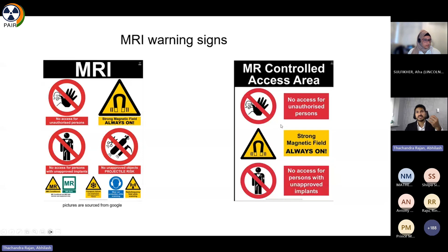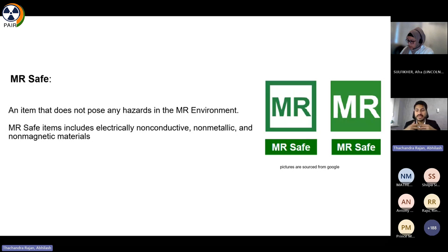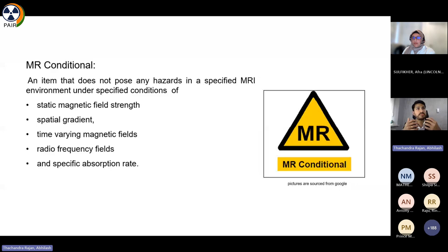What is MR safe? Any item that does not pose any hazards in the MR environment, which includes non-magnetic, non-metallic, or non-conductive materials. MR conditional items are similar to MR safe items, but there are conditions for them. Those conditions relate to field strength, spatial gradient, time varying magnetic field or the gradient field, radio frequency fields or the RF fields, and specific absorption rate. MR unsafe items are not allowed inside the MR environment. Mostly they will be ferromagnetic materials, and they will be denoted by this symbol. Also, any items kept in the MR control access area or in the MR environment should be labeled according to MHRA.